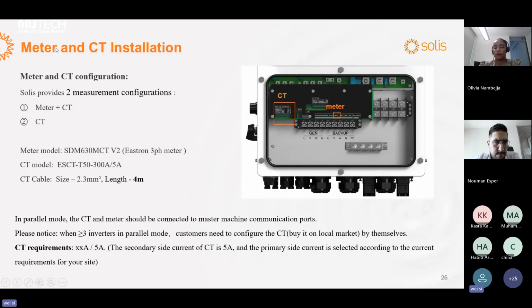For the measurement, we provide two measurement configurations. One is meter and CT configuration, and one is only CT. For the CT cable, the default length is 4 meters. One thing to notice is that when you want to connect more than 3 inverters in parallel mode, you need to configure the CT by yourself. For the CT requirements, the secondary side current of the CT is 5 amperes, because the current range is not enough for the parallel mode.